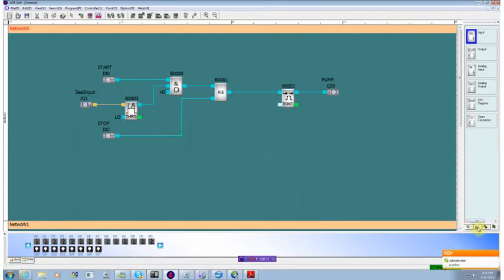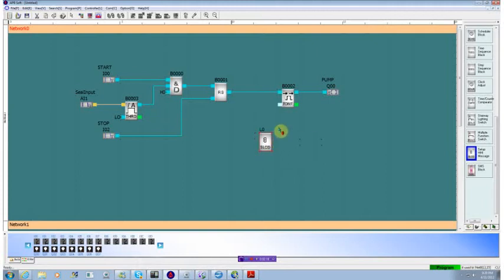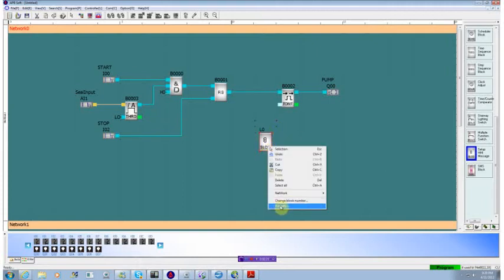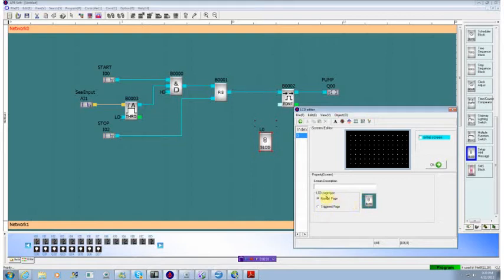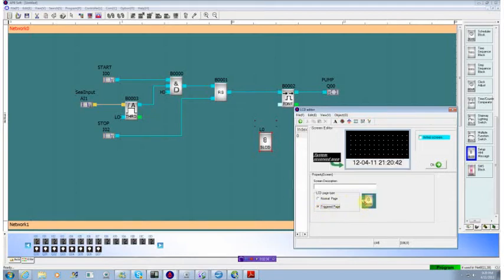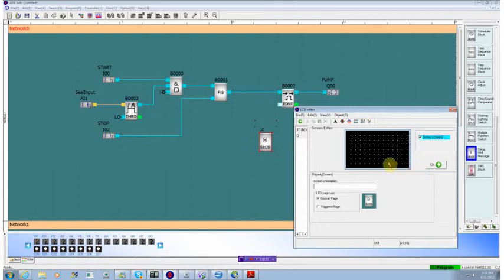What we want to do is bring some of this information up to the operator so they can see it as the system is running. We'll go over to our digital capabilities and we see at the bottom we have this setup HMI block. We'll bring one of those over. Right click it and go down and look at the properties. We see that there's actually two types of pages we can display. There's a normal page, which the operator would get at using the scrolling buttons, and a triggered page. If we select that, it brings up an input. When this input goes active, it will trigger this page up and that would be used for alarm conditions. Initially we want just a normal operating screen. By selecting the initial screen option, means this will be the first screen that comes up when the system powers up.